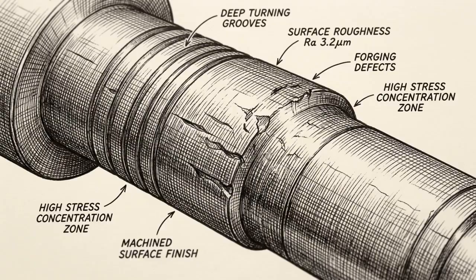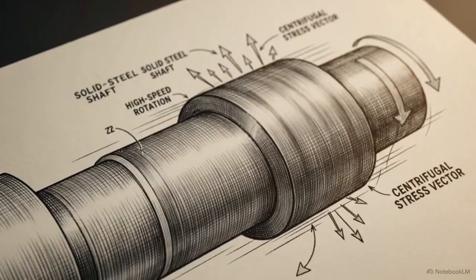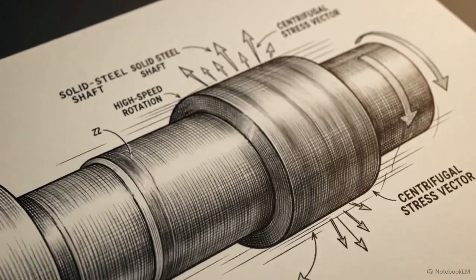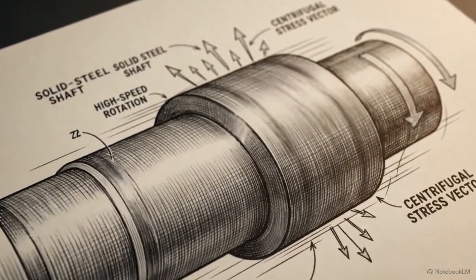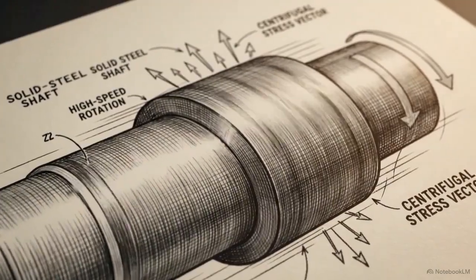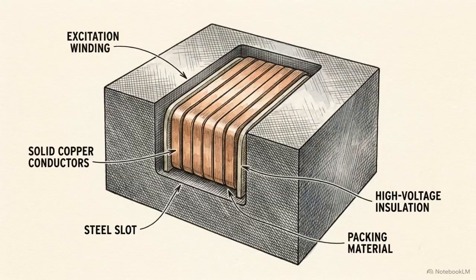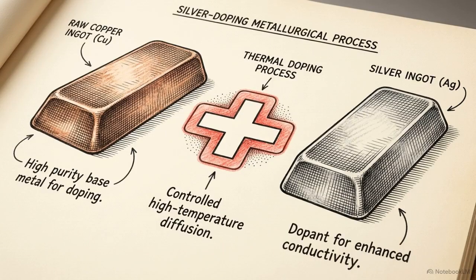The rotor shaft itself faces severe mechanical constraints. To survive the immense centrifugal stress of spinning at 3,000 RPM, the entire body is machined from a single solid steel forging. The rotor's excitation winding is seated within the slots of this steel body. Standard copper would warp under these combined forces. Instead, the winding is manufactured using copper doped with silver, which maintains strict mechanical stability at the rotor's maximum working temperature of 115 degrees Celsius.